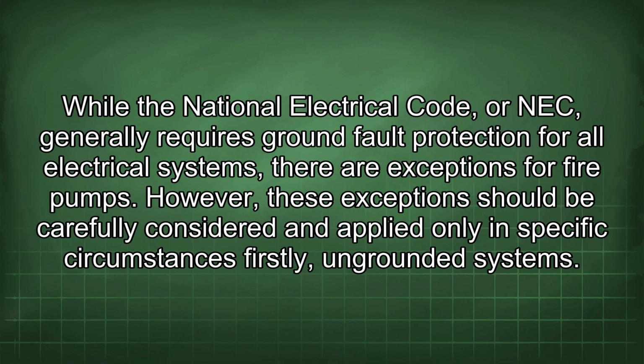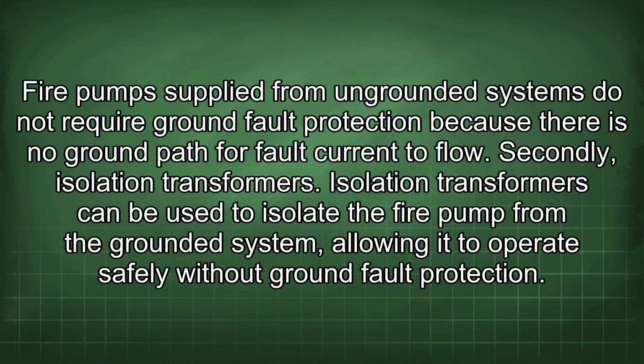While the National Electrical Code, or NEC, generally requires ground fault protection for all electrical systems, there are exceptions for fire pumps. However, these exceptions should be carefully considered and applied only in specific circumstances. Firstly, ungrounded systems. Fire pumps supplied from ungrounded systems do not require ground fault protection because there is no ground path for fault current to flow. Secondly, isolation transformers. Isolation transformers can be used to isolate the fire pump from the grounded system, allowing it to operate safely without ground fault protection.